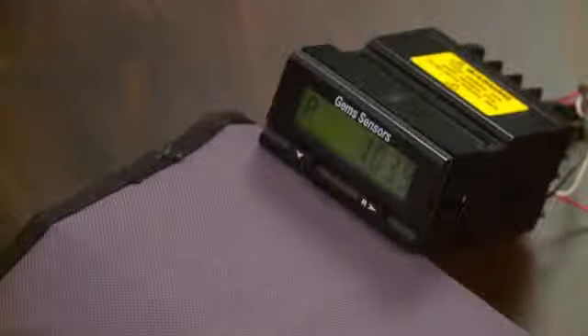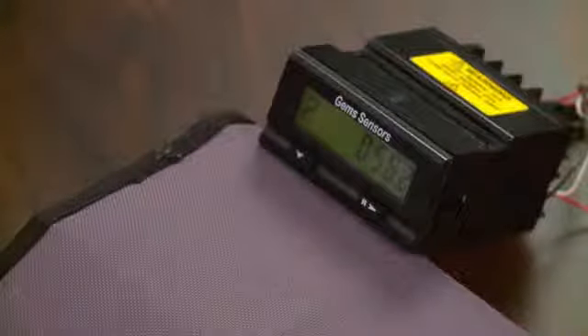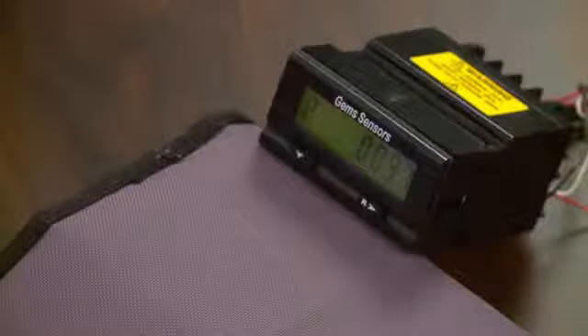The next thing to take a look at is, let's take a look at what is our actual rate. Right now, nothing's going through the sensor. It's 0.000 gallons per minute. As I blow through it, it changes. It has a little built-in delay, and as you can see, we made it up to 1 gallon a minute it spun, and it, again, decays on down to 0. The meter is now scaled with the sensor, and it is working.